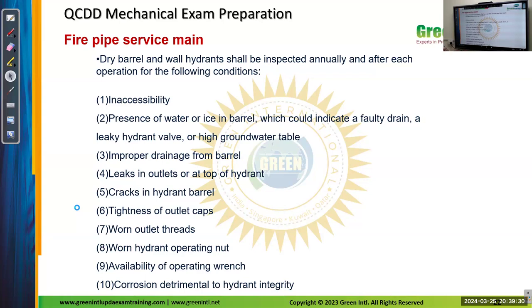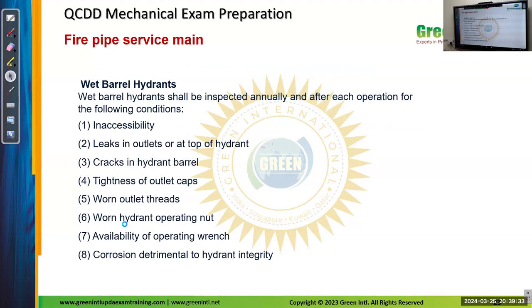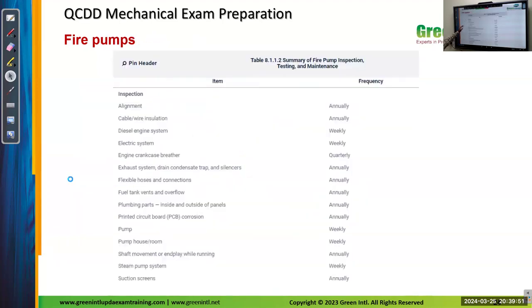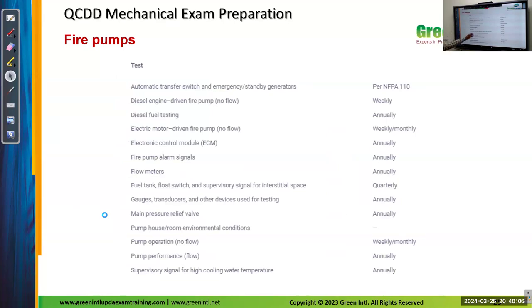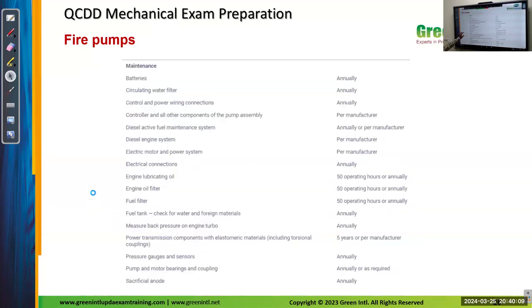And if it is working or not, we will just sign it and produce a report. Wet barrel systems, this is the one which we are using here: leaks in the outlet, inaccessibility, cracks, tightness of outlet, worn out threads, availability of operating wrench, corrosion detrimental to hydrant integrity. So it's like a checklist. Then fire pump inspection. Of course, you can expect one question from this, for sure. These are all the inspection details with their frequency, the testing details with their frequency, and the maintenance details with their frequency.